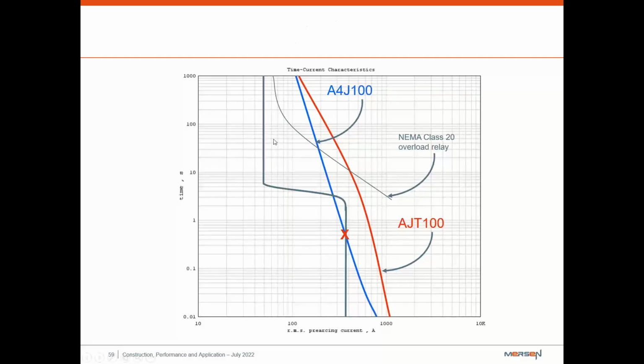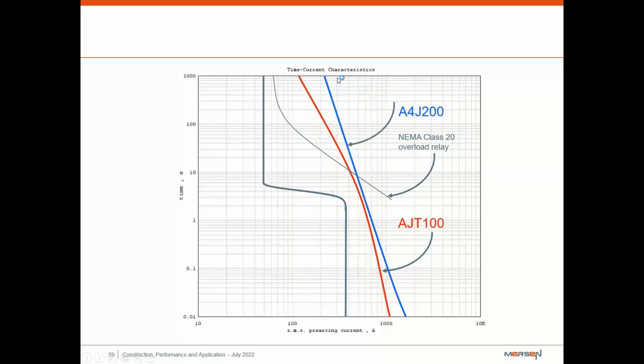So according to 430.52, we're allowed to go up to 300%. If we move that to the 300%, it'll take that A4J and move it to an A4J200, which will allow us to stay. You can see that the overload relay will actually open before that, or faster. The overload will open faster than the A4J, and that's what we want. We want this thing to go into normal operation before we have any kind of a fault.